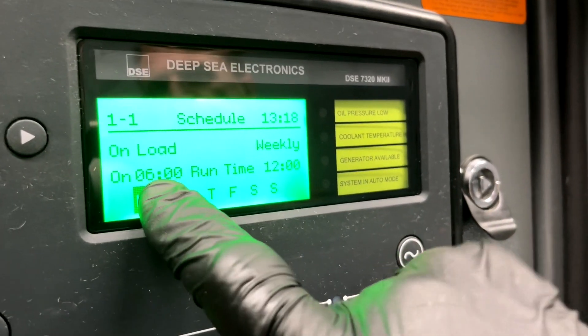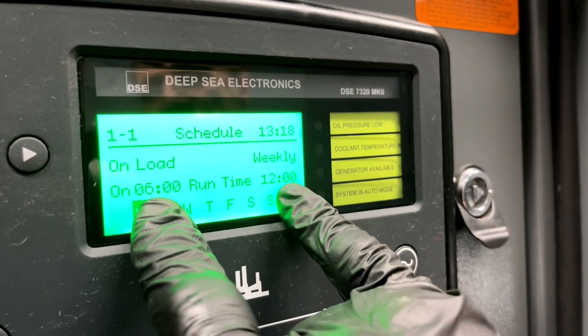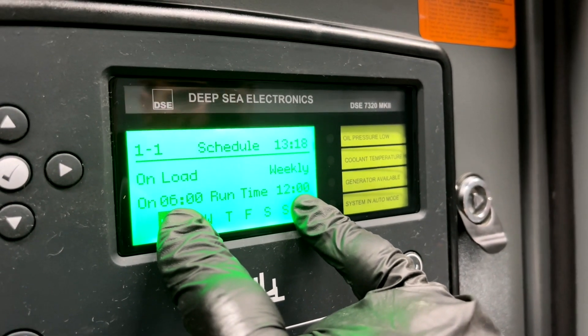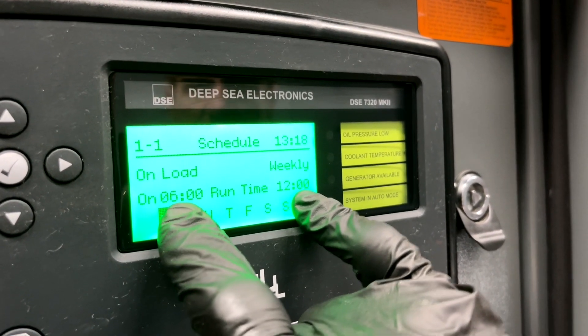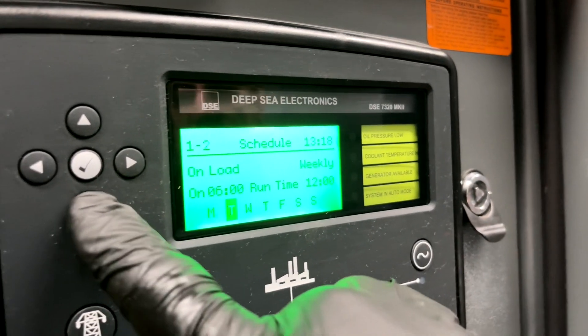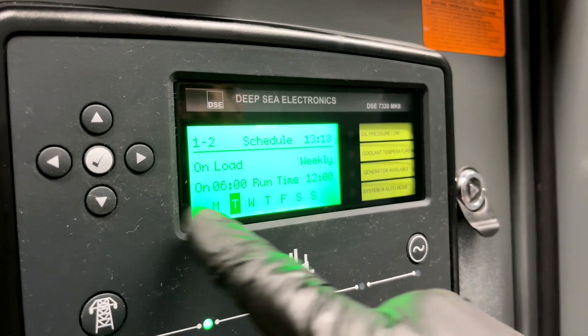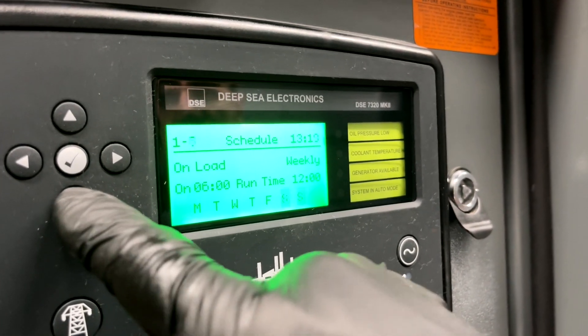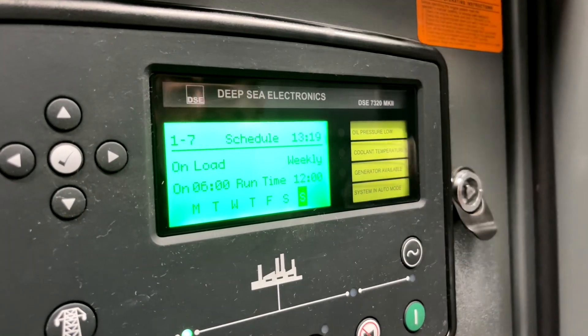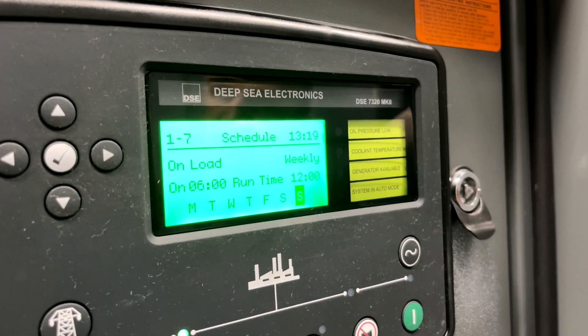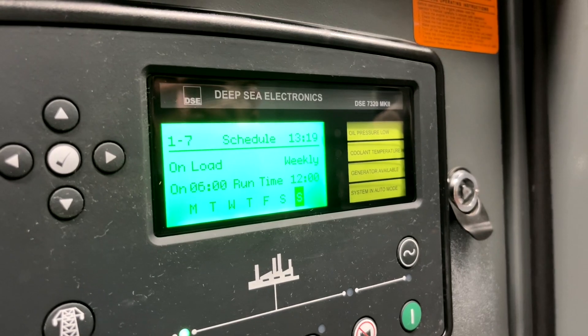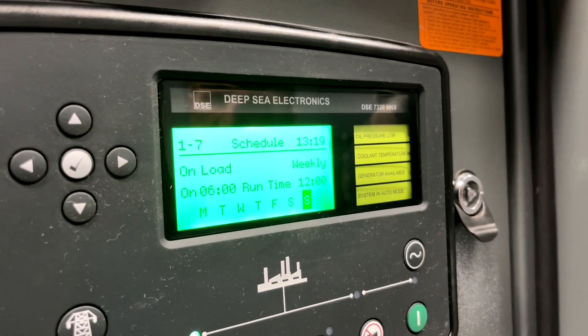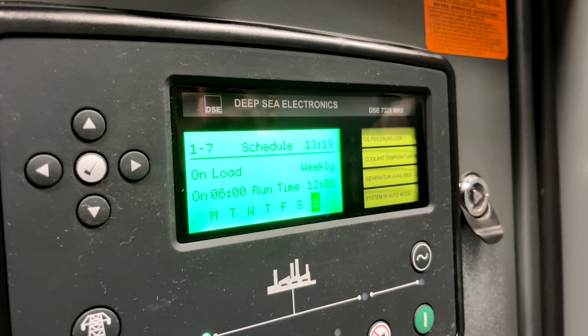Runtime is for how long the generator will run. So 6 a.m. running for 12 hours means it will turn off at 6 p.m. We have this set the same for every day. So this generator turns on every day at 6 a.m. and turns off at 6 p.m. every day. That's how it's programmed.